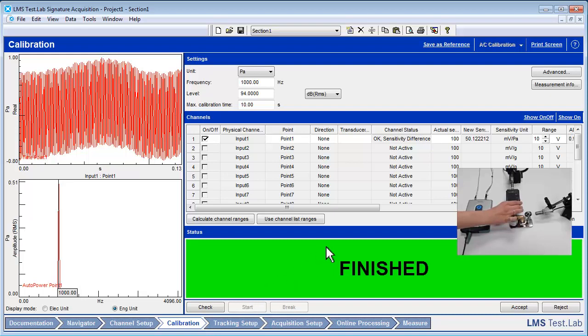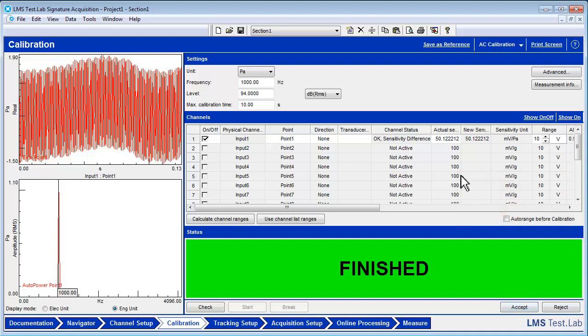While the microphone is being calibrated, the sensitivity being measured will be shown under New Sensitivity in the Channels window. Once the status shows finished, press Accept to use the newly measured sensitivity values for the microphone. The new sensitivity will replace the actual sensitivity in both the Channel Setup Worksheet and the Calibration Worksheet automatically.